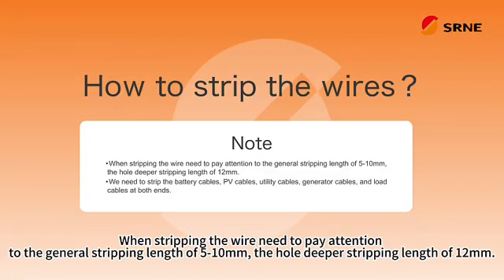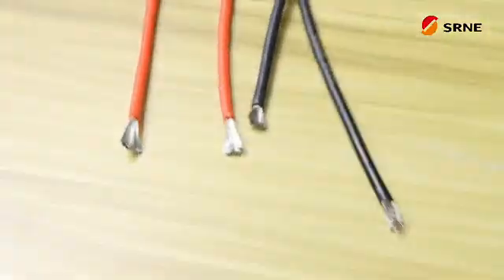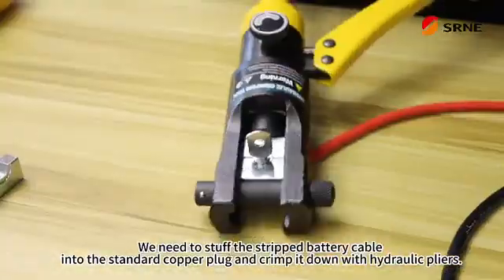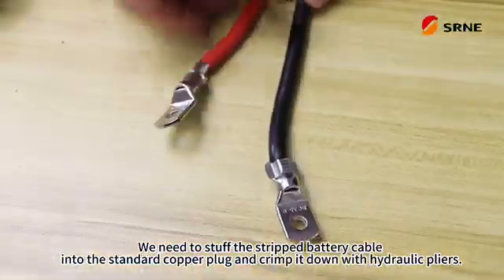When stripping the wire, pay attention to the general stripping length of 5 to 10 mm and the hole deeper stripping length of 12 mm. Stuff the stripped battery cable into the standard copper plug and crimp it down with hydraulic pliers.